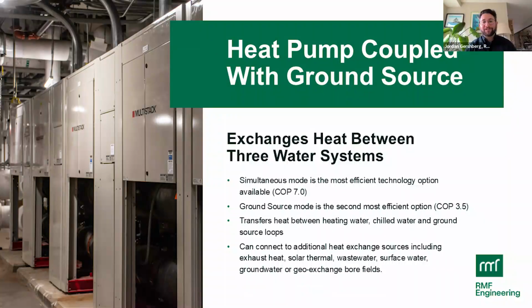Sometimes that load isn't going to be balanced, so adding a ground source heat exchanger is similar to having a cooling tower in a traditional chilled water system. The difference is you're no longer just exhausting that heat to the atmosphere, never to be seen again. You're using the core of the earth to act as a thermal battery, storing some of that energy over time so you can extract it again when your thermal loads are more balanced for the connected equipment.